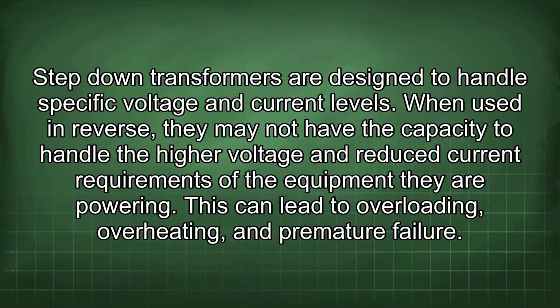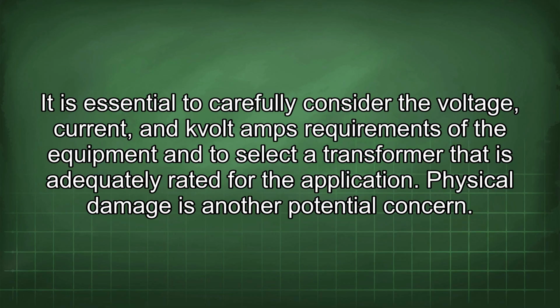Limited capacity can also be a problem. Step-down transformers are designed to handle specific voltage and current levels. When used in reverse, they may not have the capacity to handle the higher voltage and reduced current requirements of the equipment they are powering. This can lead to overloading, overheating, and premature failure. It is essential to carefully consider the voltage, current, and kVA requirements of the equipment and to select a transformer that is adequately rated for the application.